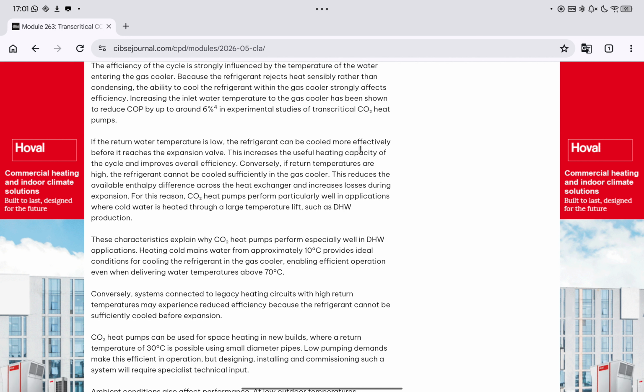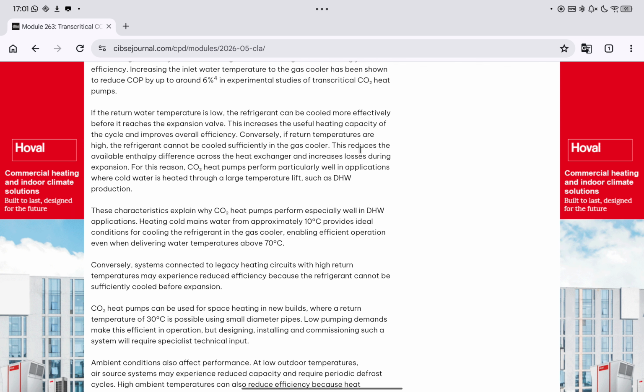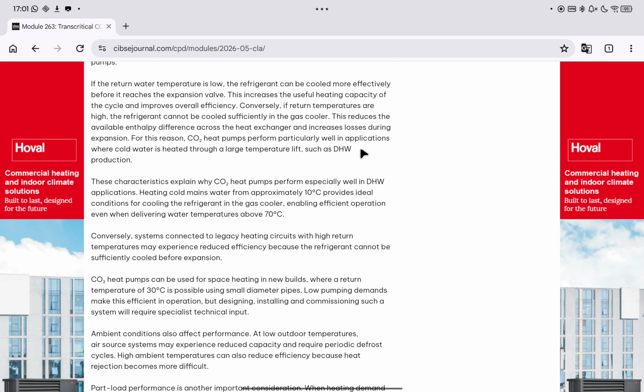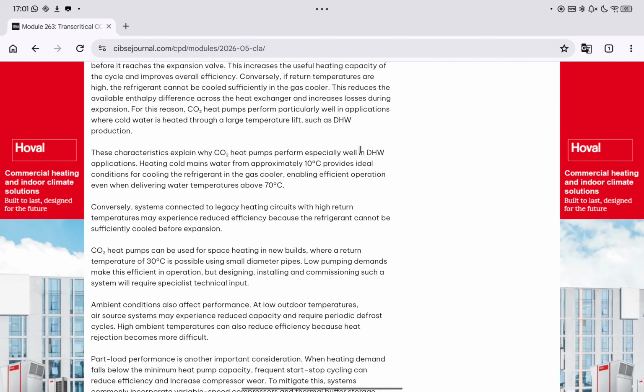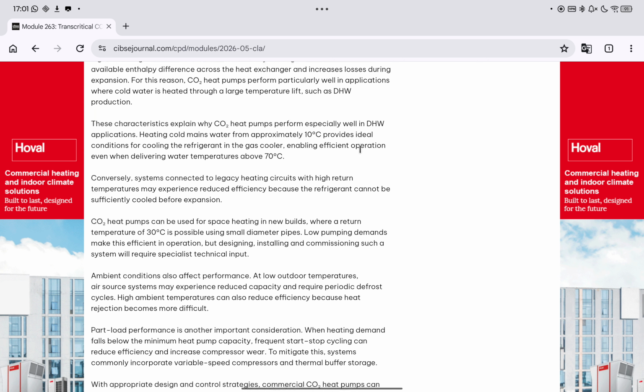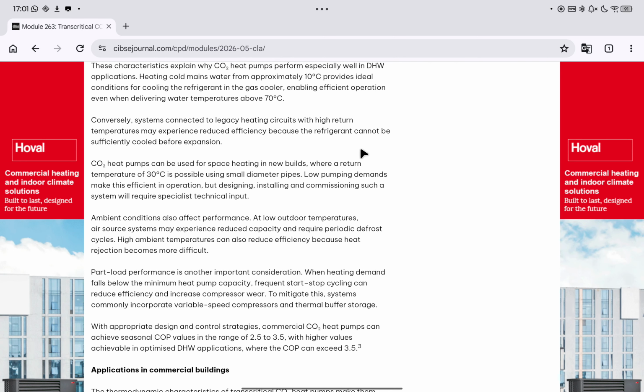Heating cold mains water from approximately 10 degrees C provides ideal conditions for cooling the refrigerant in the gas cooler, enabling efficient operation even when delivering water temperatures above 70 degrees C. Conversely, systems connected to legacy heating circuits with high return temperatures may experience reduced efficiency because the refrigerant cannot be sufficiently cooled before expansion. CO₂ heat pumps can be used for space heating in new builds, where a return temperature of 30 degrees C is possible using small diameter pipes. Low pumping demands make this efficient in operation, but designing, installing and commissioning such a system will require specialist technical input. Ambient conditions also affect performance.